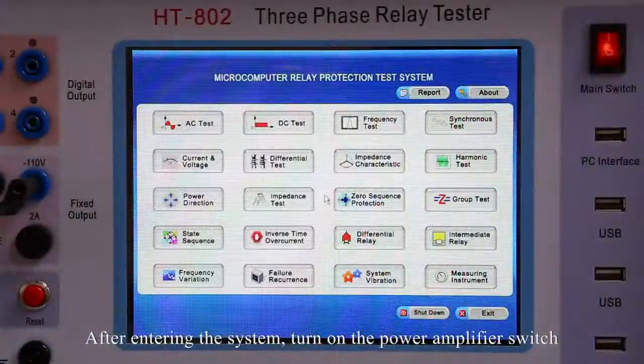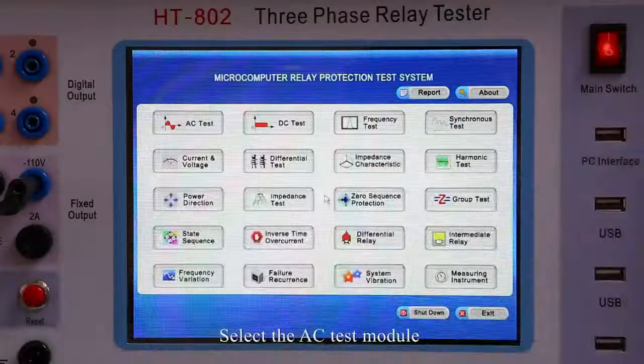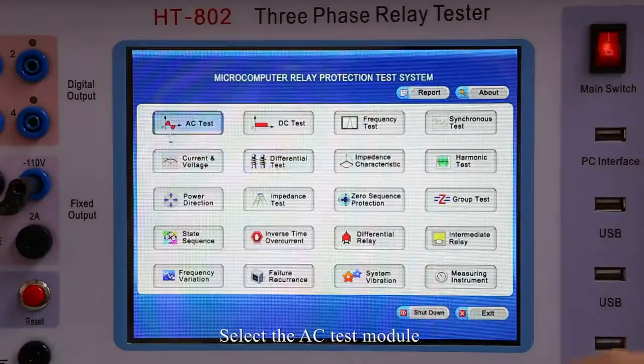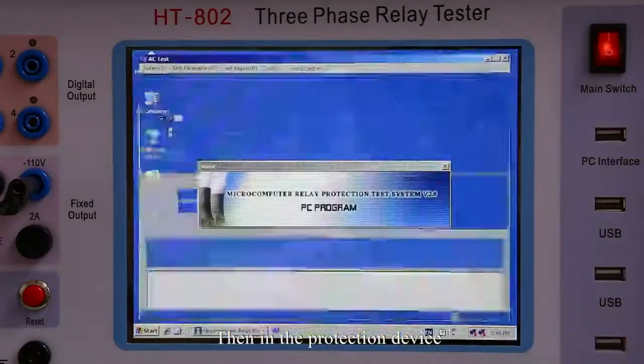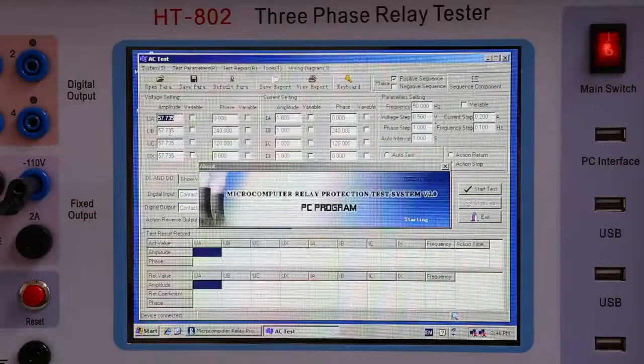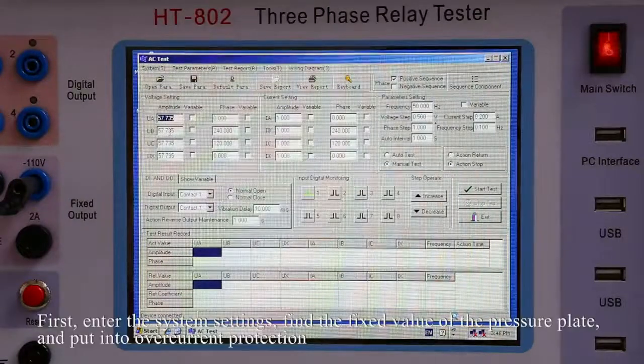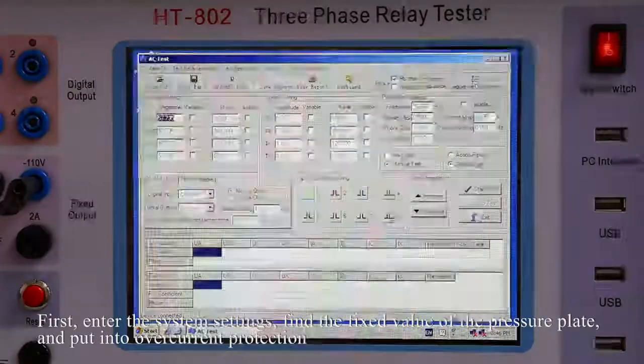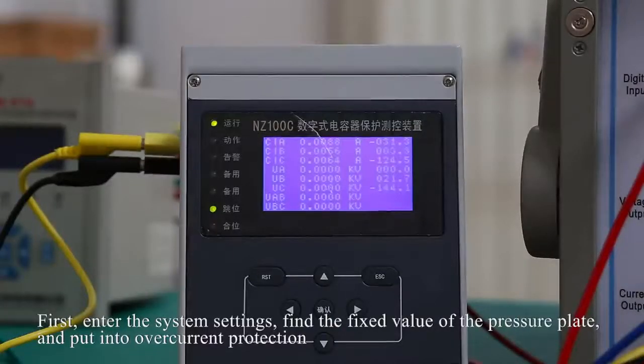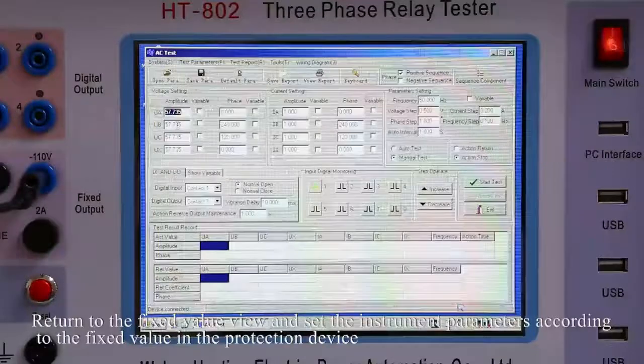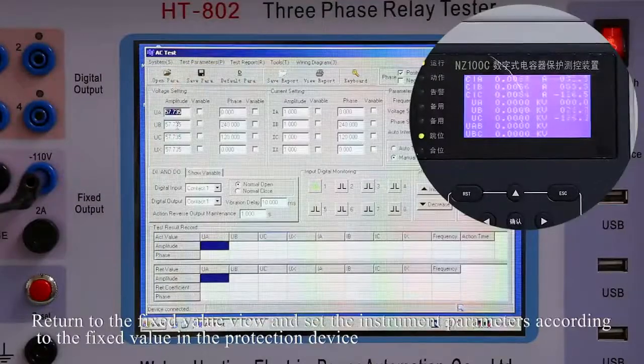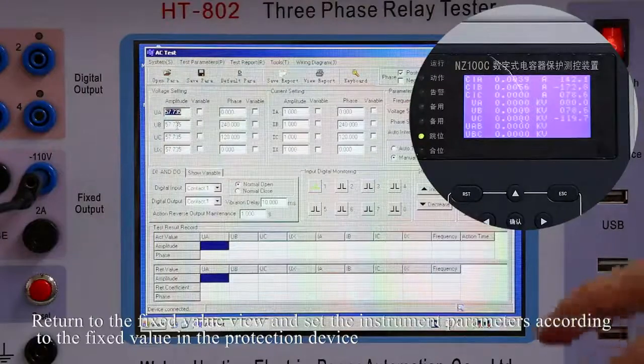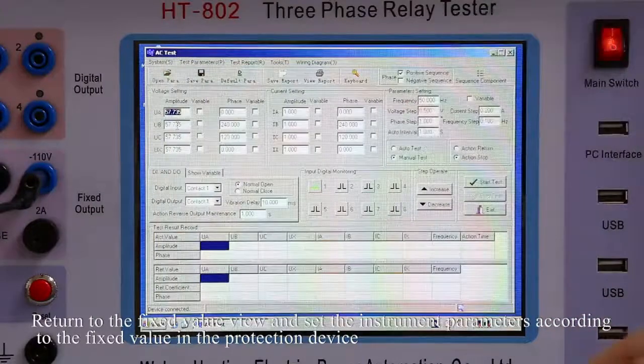After wiring, turn on the power supply of the relay protection tester. After entering the system, turn on the power amplifier switch. Select the AC test module. Then, in the protection device, first enter the system settings. Find the fixed value of the pressure plate and put it into overcurrent protection. Return to the fixed value view and set the instrument parameters according to the fixed value in the protection device.